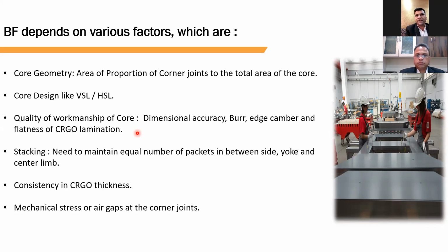If we are placing that lamination on an uneven platform, then stress is definitely going to occur in that CRGO lamination, because if your surface is not uniform, you are stacking all the laminations one by one, and that load will impact the bottom lamination, producing stress which will deteriorate the performance of the CRGO.